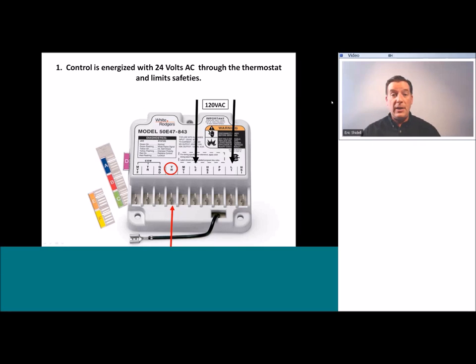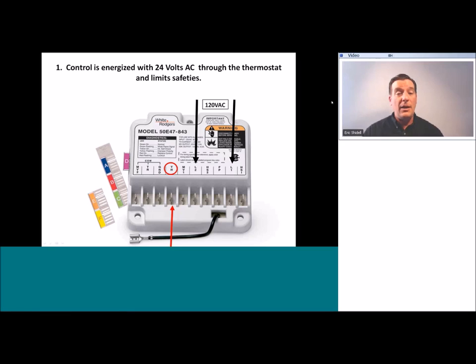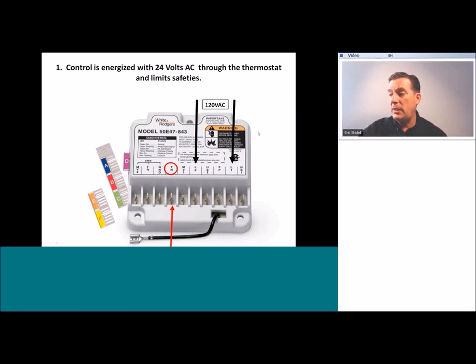Let's take a look at the non-integrated hot surface ignition control module. The function of this is very similar to what we just saw, with a couple of differences. First, the ignition source is not a spark — it is a hot surface igniter. The hot surface igniter is a 120-volt device operated off of 120 volts AC. In order for the ignition controller to operate that device, it has to have 120 volts AC. So on a non-integrated HSI control you will find 120 volts between terminals L1 and L2.